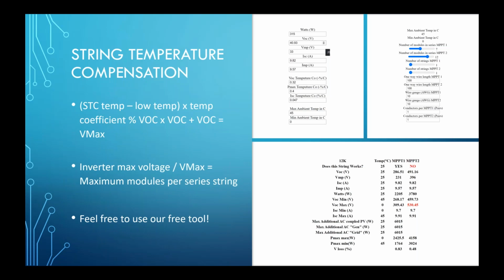The good news is it works like this. Let's say you have a Hanwha Q-cell panel and it's 360 watts. You pull up the data sheet and it says VOC 42.5. So it's got 42.5 volts open circuit. Well, you're thinking to yourself, I want to use 10 of these in a string, right? So for what I say the panels were 360, you'd have to do the math, 3.6 kilowatts, et cetera. So you look at the 42.5 voltage open circuit, you want to use 10 panels, 42.5 times 10 is now 425. That's great.